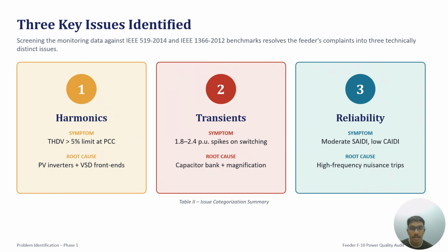This is phase one of our framework, problem identification, where we screen the monitoring data against IEEE 519-2014 and IEEE 1366-2012. The feeder's complaints resolve into three technically distinct issues, summarized in Table 2.